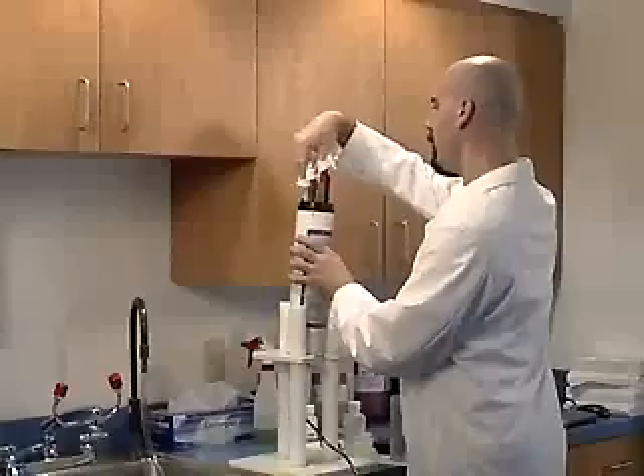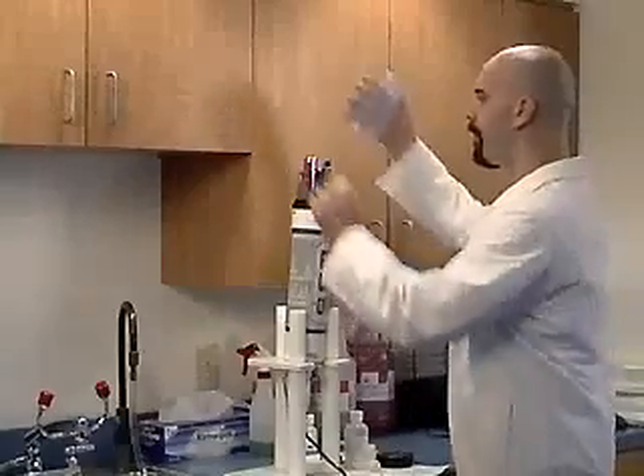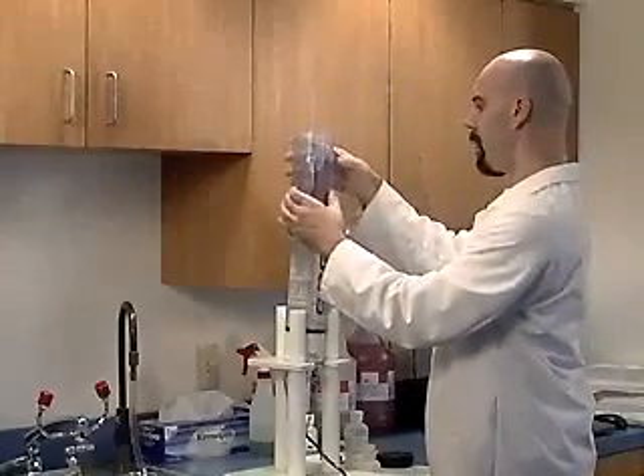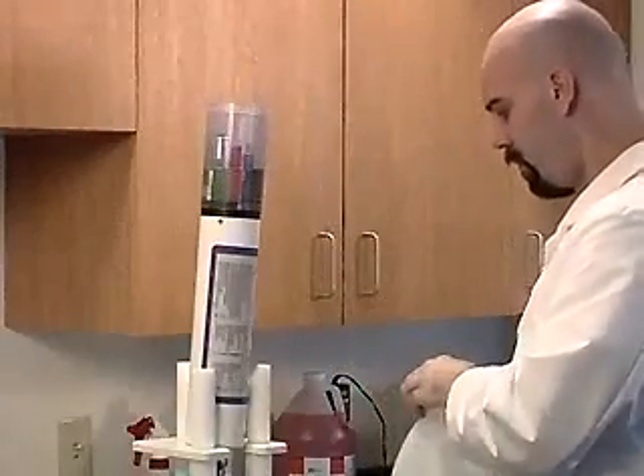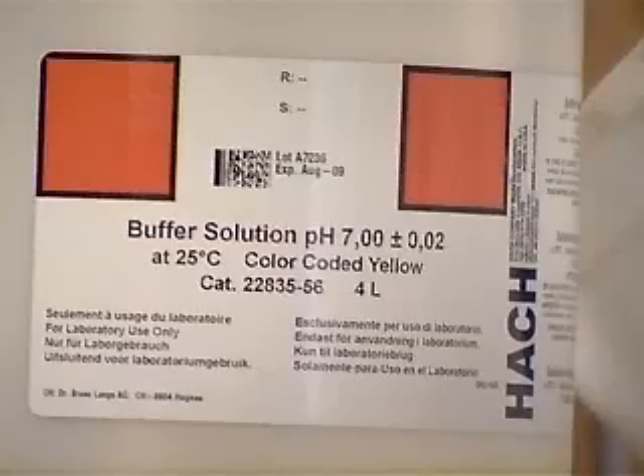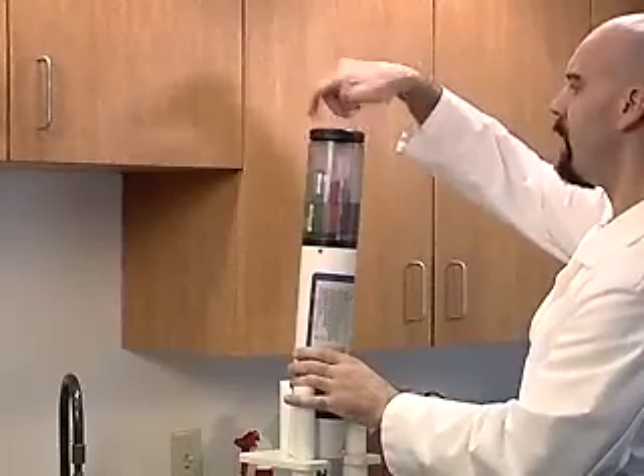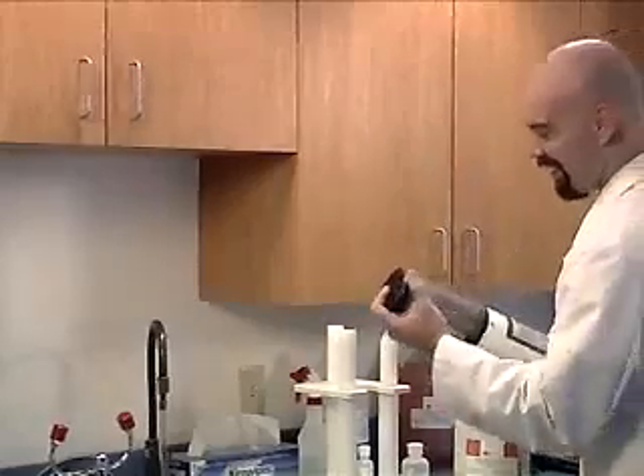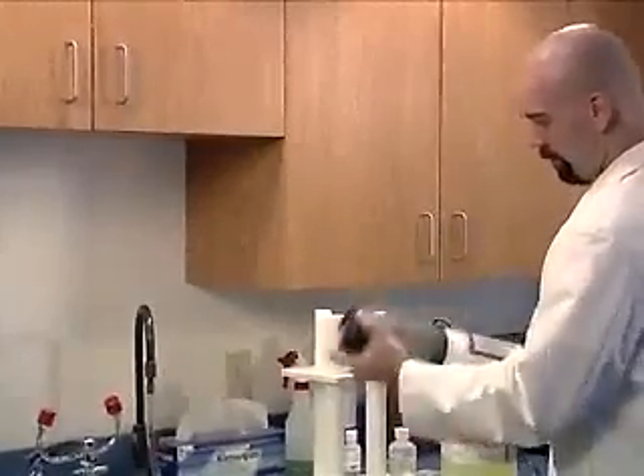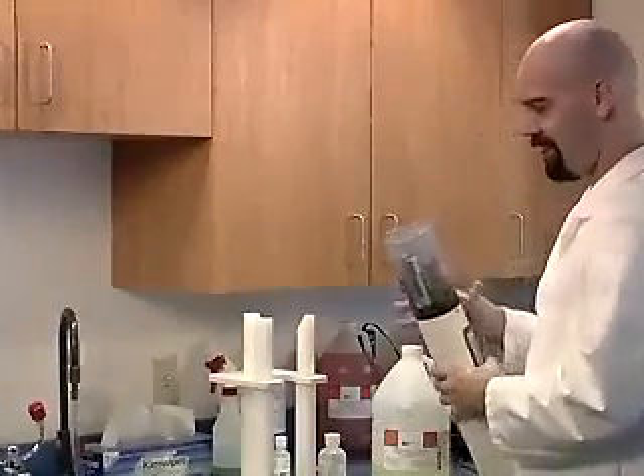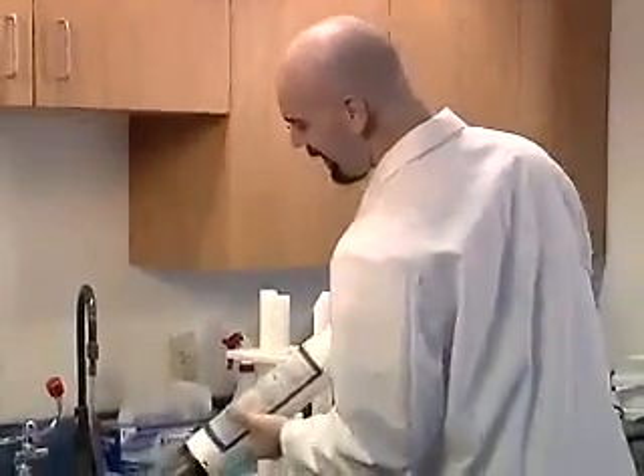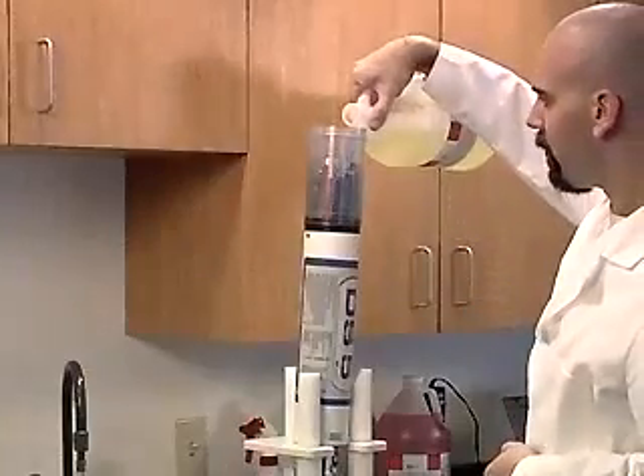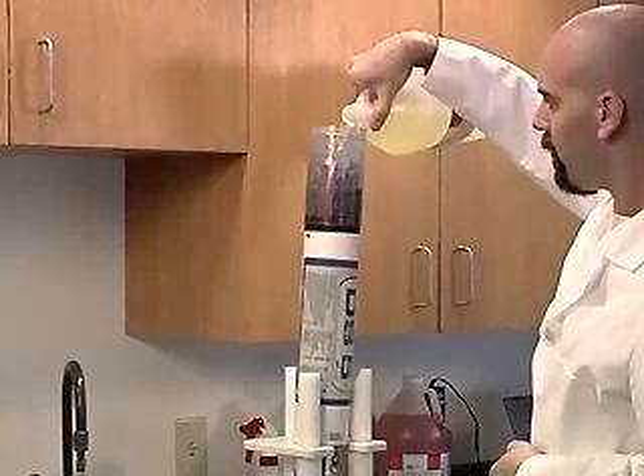Rinse and dry the sensors and attach the storage calibration cup. Fill the cup about 25% with pH buffer 7 and screw the storage cap on. Shake for 6 seconds. Remove the storage cap and pour the buffer 7 out. Fill the cup with buffer 7 again, this time over the top of the pH sensor. Wait 1 minute for the readings to stabilize.